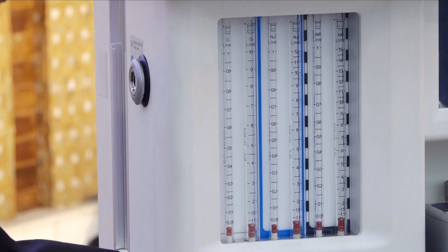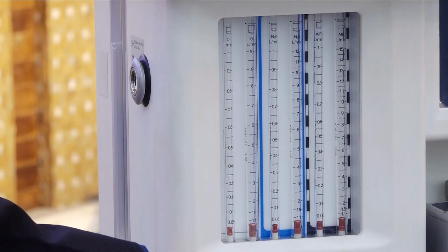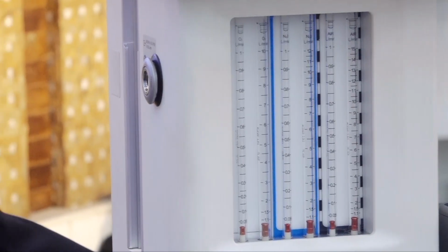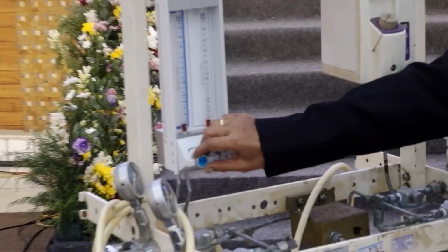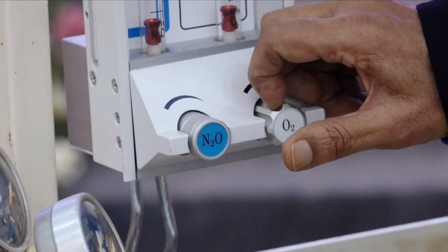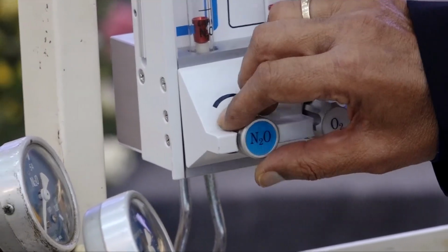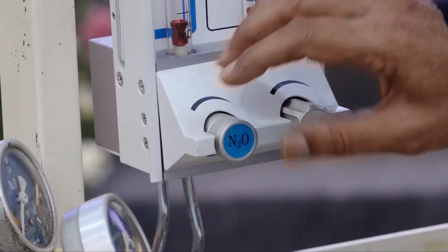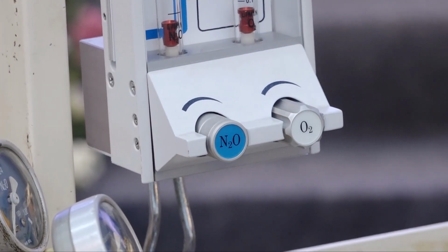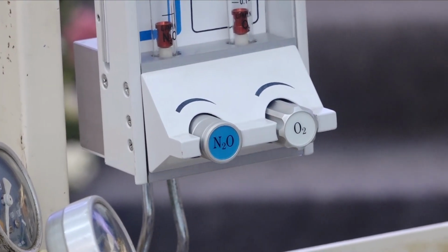And these flow control knobs, whether in the newer machines or the older machines, are also color coded and touch coded. I need not see. If I am touching here oxygen, I know, because the flutes are wide and the color is white, and these flutes are narrow. And that's how, by touching also, they are touch coded and color coded, which you should know.